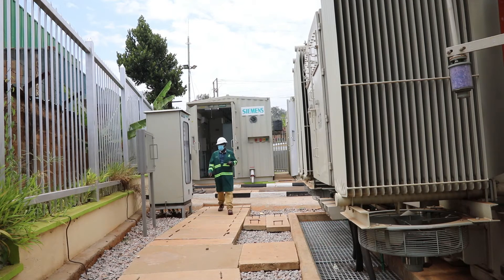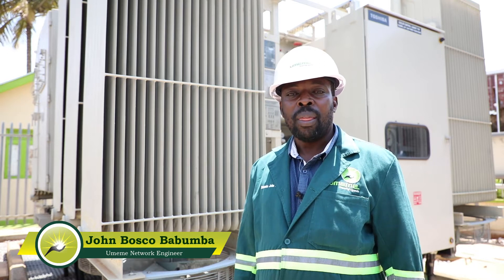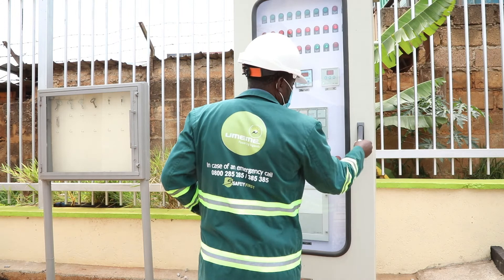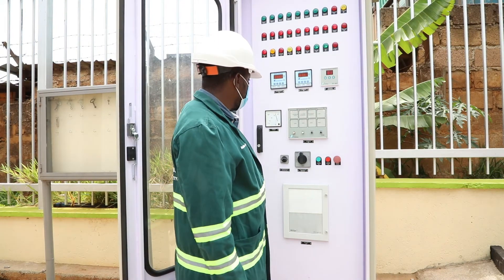There was a need for this new station because we used to have only one line from Rogogo. Its capacity had reached seven megawatts. Seven megawatts was too big for that line — it used to trip and go off all the time, sometimes taking like seven hours out in a day. So the need was to break that line so that we can have different lines to supply this growing area of Nakawa.